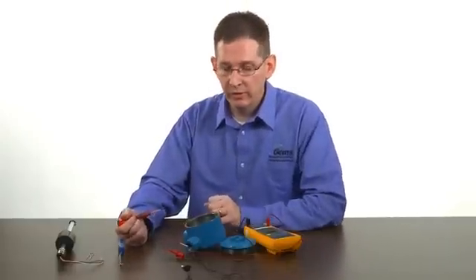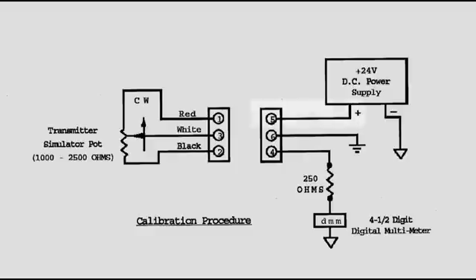To wire this up properly you'll take your 24 volt positive DC into pin 5, pin 4 will go to your multimeter, and your common leg of the multimeter back to your negative leg of the DC power supply.